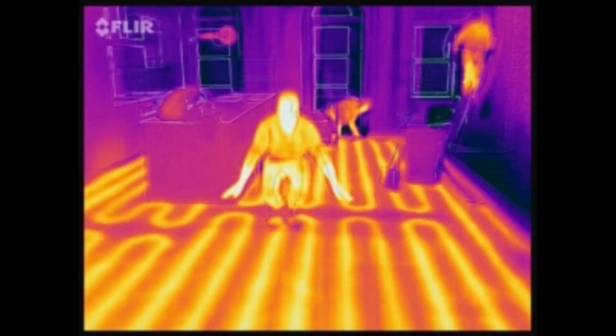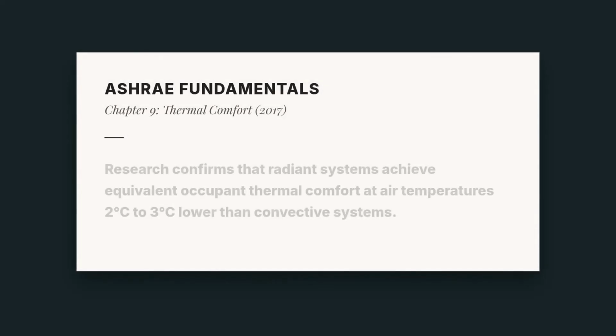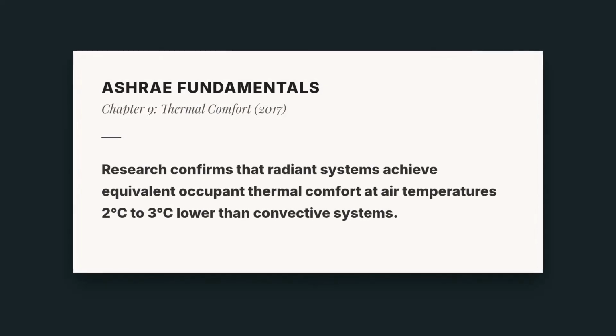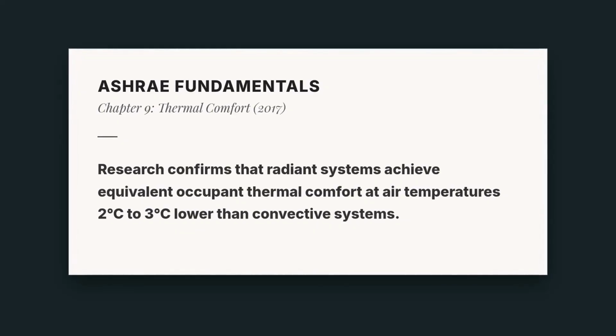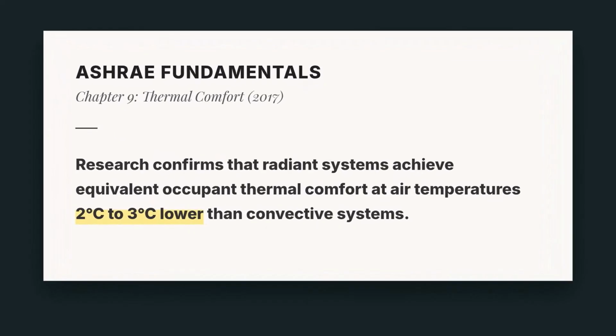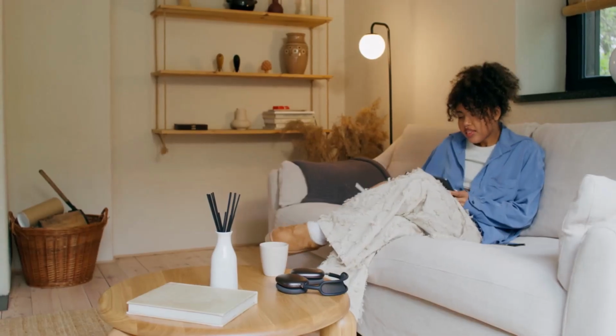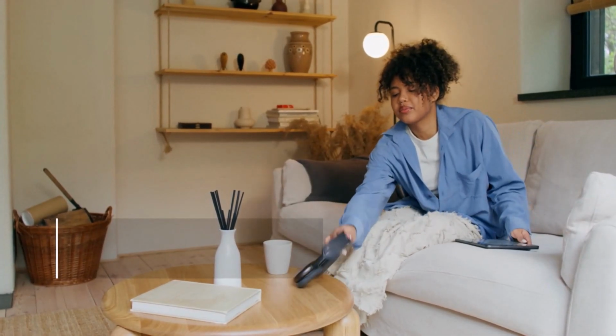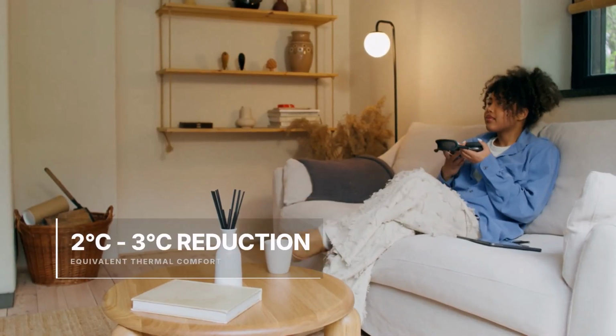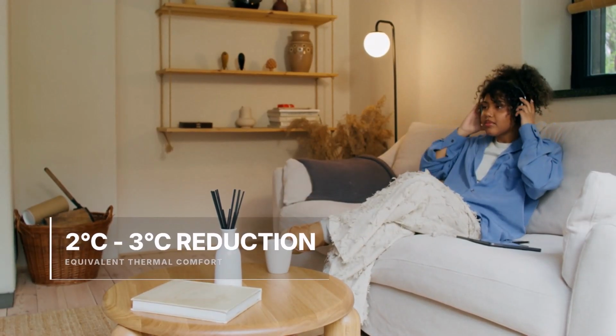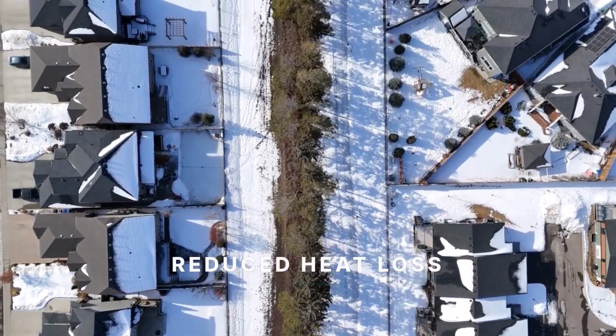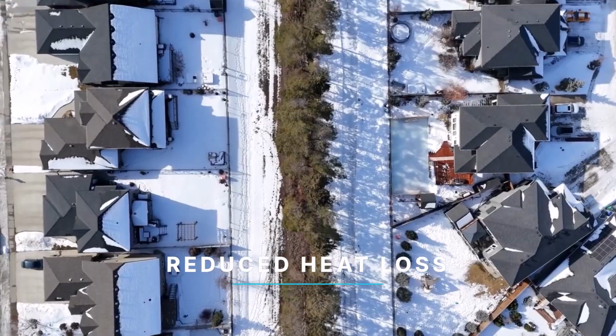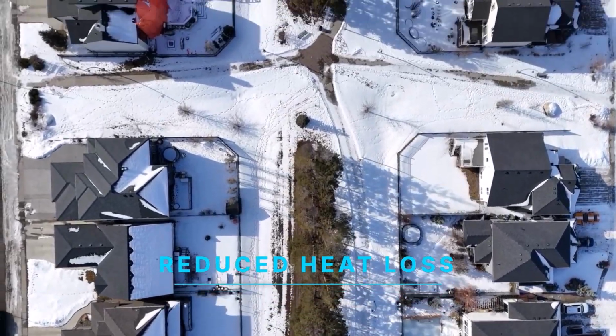It heats the concrete mass of the slab. The concrete slab radiates heat upward into the room from its entire surface area. The comfort distinction is measurable and documented. The American Society of Heating, Refrigerating, and Air Conditioning Engineers, ASHRAE, published its research in 2017, confirming that radiant floor heating achieves equivalent occupant thermal comfort at air temperatures 2 to 3 degrees Celsius lower than forced air systems. The lower air temperature required reduces the temperature differential, which directly reduces heat loss through the building envelope.